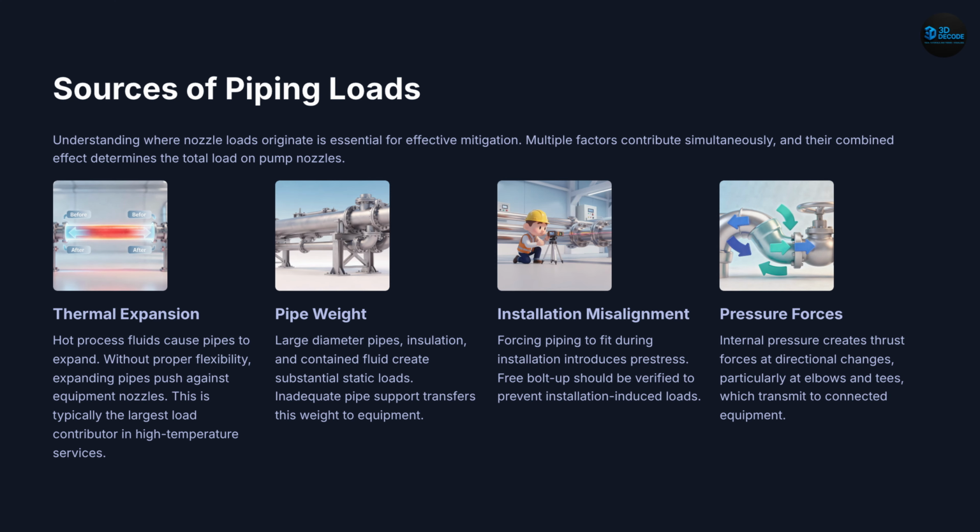Slide 5. Sources of loads. Nozzle loads come from multiple sources: thermal expansion of piping, pipe weight, installation misalignment, and pressure forces all contribute. In high-temperature systems, thermal expansion is the dominant factor.